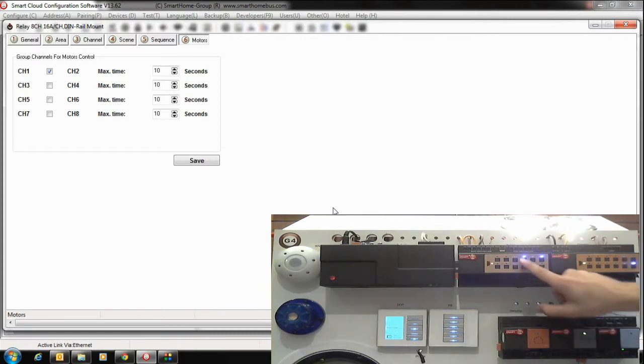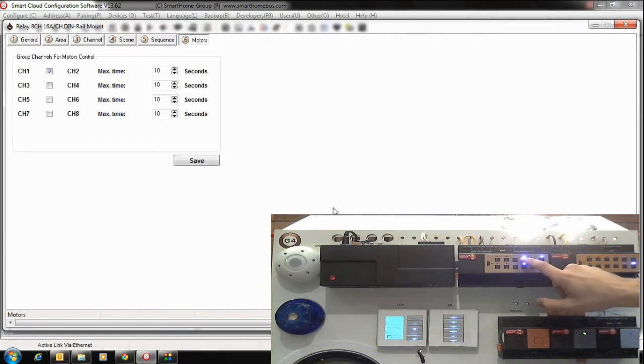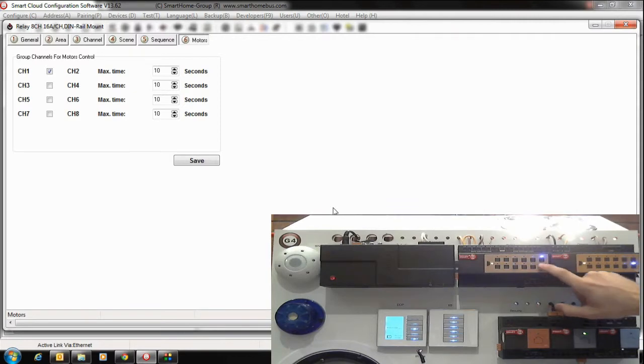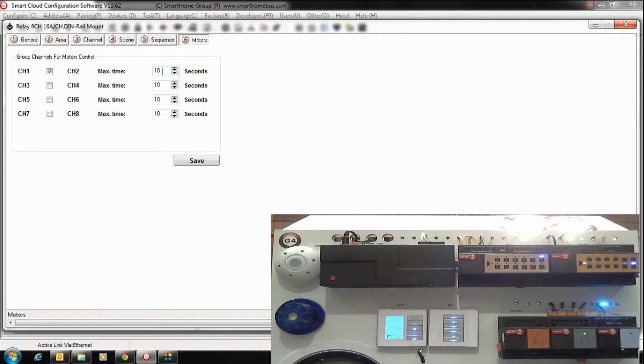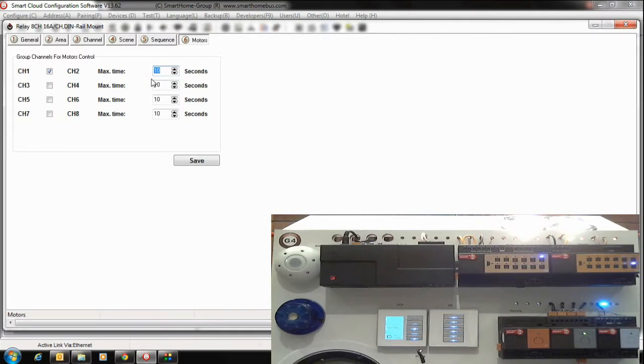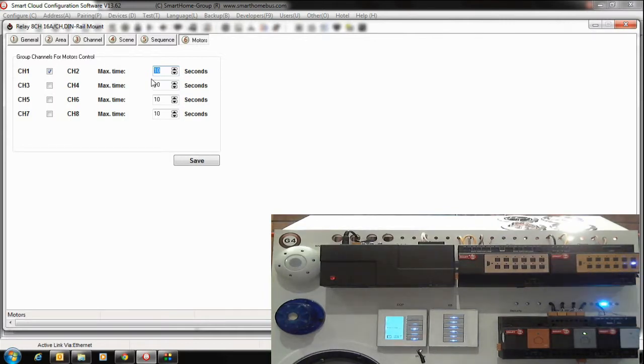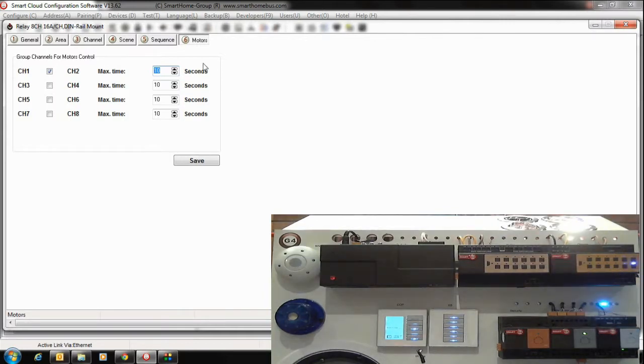Here in the cross and these ones in the cross, the maximum time, how much time you want to fully open or fully close. The maximum time, that means here after 10 seconds this one will switch off, whatever this one, the motor. After 10 seconds will switch off, so this is the maximum time you want to activate this channel.